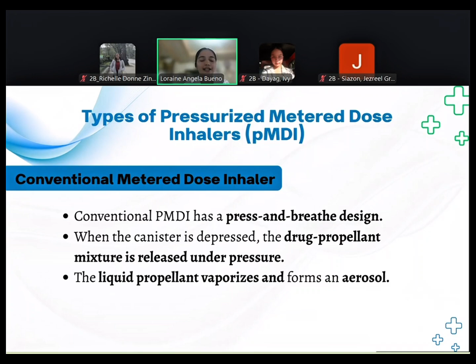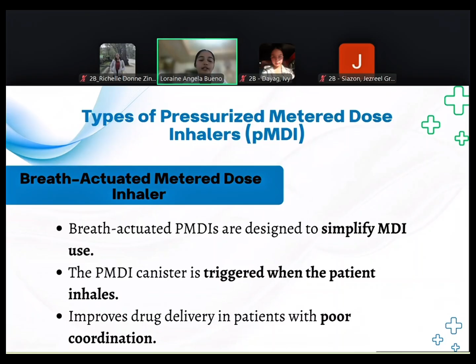On the metering valve and spray characteristics, metering valve volume ranges from 25 to 100 microliters and delivers 50 micrograms to 5 mg of drug per actuation. Hydrofluoroalkane versions have a warmer spray temperature. On the breath-actuated metered dose inhaler, breath-actuated pressurized metered dose inhalers are designed to simplify metered dose inhaler use. The canister is triggered when the patient inhales, which improves drug delivery in patients with poor coordination.